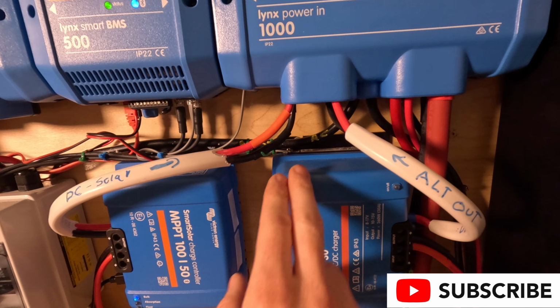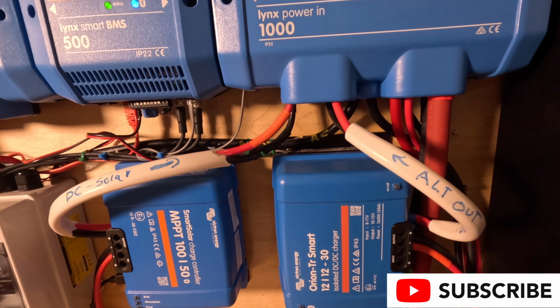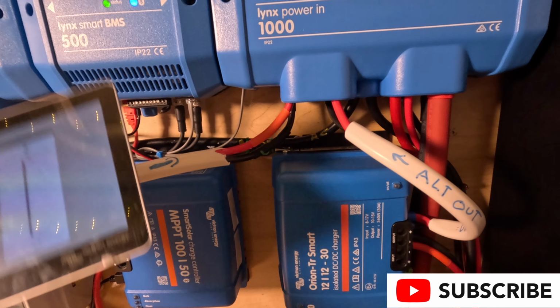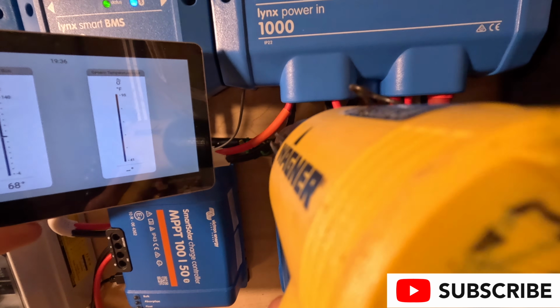It's a good location for our temperature probe, which is going to activate our relay, which is going to activate our fans. So we'll do a little test here with a heat gun. We will heat up our probe and see if we get some action.